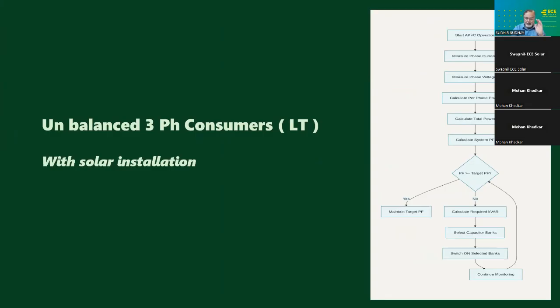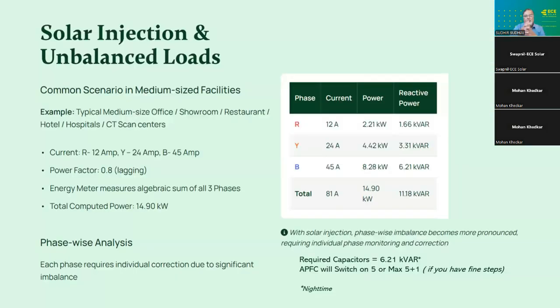Now comes the question of how an unbalanced load, typically again with solar power injection, will behave. As I said, 20 kilowatt and above. That means these are all small shops, medium-sized offices, maybe showrooms, maybe restaurants, maybe hotels, hospitals. All these are 20 kilowatt and above LT consumers. Now, as we discussed in the earlier case, it is quite possible that your contractor has done a very good job, but because of the usage pattern, switching on and off, your current requirement per phase is differing, and so is the reactive power requirement differing from time to time.